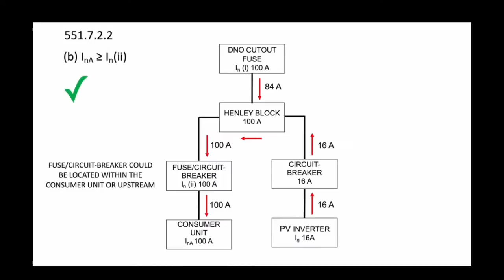I think it's worth pointing out that although the drawing on the screen shows the fuse or circuit breaker upstream, if your consumer unit had a double pole main switch in there, you could take that out and replace it with a 2-pole circuit breaker. So you wouldn't even have to put another device upstream, and I personally think that would be a better solution. Before someone says, by changing that, has it been type tested for that enclosure, you've got that to deal with.